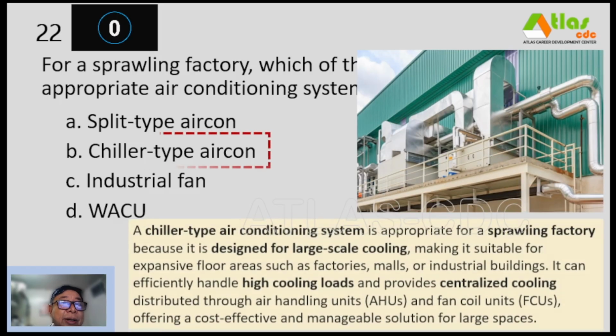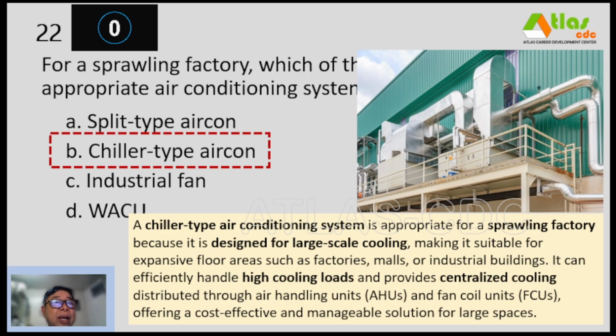And our correct answer is B. Chiller-type aircon. So a chiller-type air conditioning system is appropriate for a sprawling factory because it is designed for large-scale cooling. Make it suitable for expansive floor areas such as factories, malls, or industrial buildings. It can efficiently handle high cooling loads and provides centralized cooling distributed through air handling units or AHUs and fan coil units or FCUs, offering a cost-effective and manageable solution for large spaces.